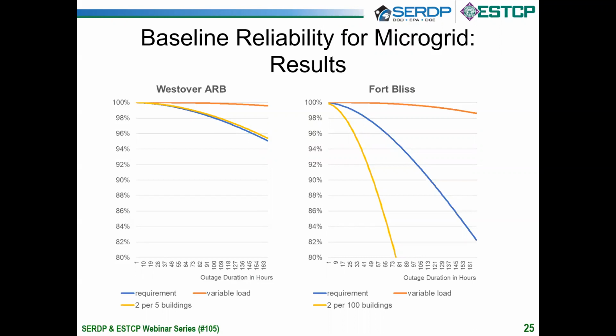So we've plotted from 1 hour up to a week in hours. So let's look first at the right at Fort Bliss. Please note that both these plots only go to 80% and are not from 0% to 100%. The blue line, which is the central line, is what was set as the minimum performance requirement for the investigators to meet.